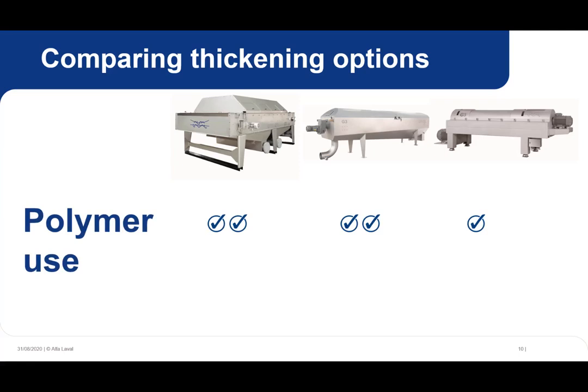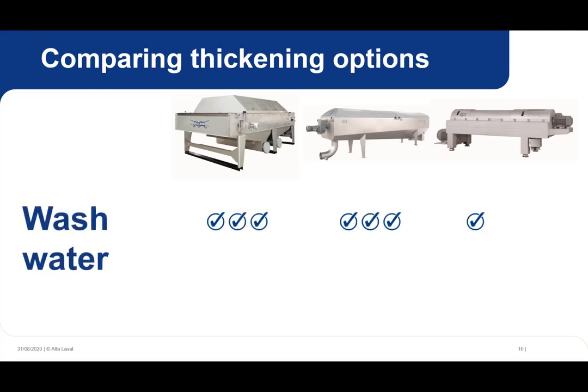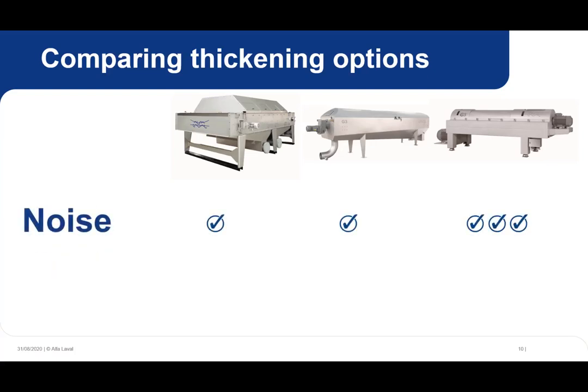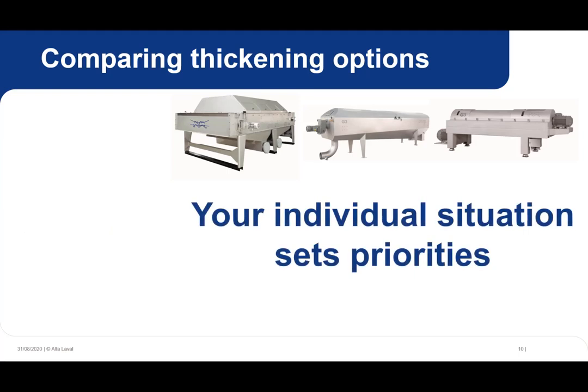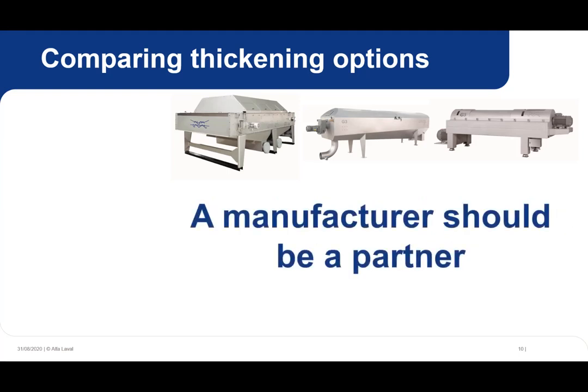Polymer use in thickening is relatively close, but some new advances in centrifuge technology can give it an advantage over other equipment. The belt thickener and drum thickener require higher amounts of wash water versus a decanter centrifuge, but because of the high speed operation of the centrifuge, it is the noisiest of the three technologies, which for some may be a consideration. Your individual situation and requirements will help determine which of these priorities matter the most. And your manufacturer's role is to listen, help evaluate your needs, and to provide options so you can make the best decision for your specific situation.